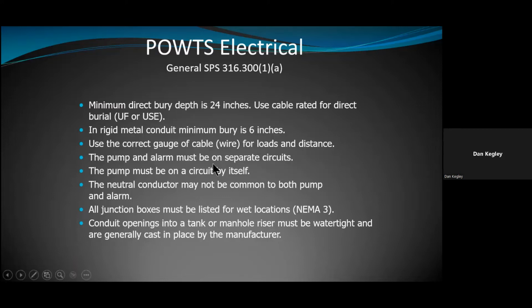And then the same thing goes for alarms too. However, alarms are a little different scenario because you don't have a constant load like you would on a motor. An alarm is really just closing a circuit to create an alarm circuit to activate and create a sound or a light kind of thing. So you don't have to be quite as picky.